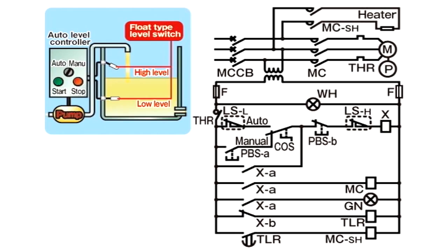Next, let's see how pump operation is resumed. First, the changeover switch is set to manual mode. When P-B-S-A is pressed, current passes through P-B-S-A to C-O-S to P-B-S-B, L-S-H, and to X, and X is excited. In the subsequent sequence operation, X-A turns on, allowing current to flow from X-A to P-B-S-B, L-S-H, and to X. As a result, X remains excited and pump operation continues, even if you take your finger off P-B-S-A.